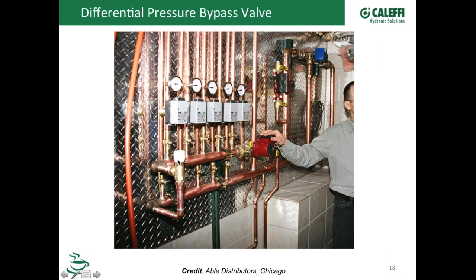It's not necessarily just the pipe size; it's going to be what your flow rate needs to be, and you've got to consider your pump as well. And that goes back, Cody, to the very first slide that I put up there, doing the simulation. If you knew what these zones required and you knew what pump you're going to select, it's going to tell you what that delta P is going to be in here. And then you'll know that the valve's selected properly. It's all about the numbers.